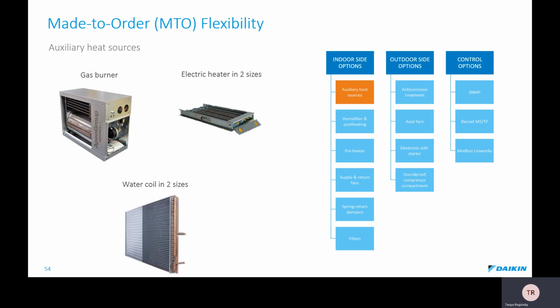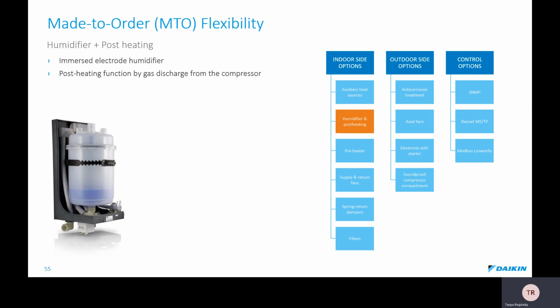The hot water coils are also available in two sizes. This can provide on average 139% and 172% of the total capacity of the unit. Most of the auxiliary heat sources can take the full capacity of the unit. It can be used in very low ambient temperatures or as a backup in case there would be a technical interruption on the heat pump side. We also have the possibility of having an immersed electrode humidifier, which is available in two sizes, depending on your required humidity and application. The post-heating function is done by gas discharge from the compressor.